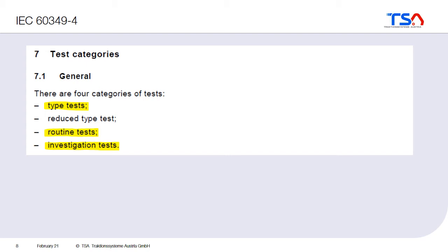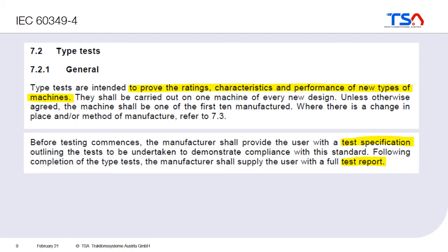There are basically two types of tests: type tests and routine tests. If you want further information you can also do investigation tests. The type test is done with one machine of every new design, and it should prove the ratings, characteristics, and performance of a new type of machine. It is also important that a test specification is sent to the customer before the tests start, and the customer is typically provided with a full test report after the tests.